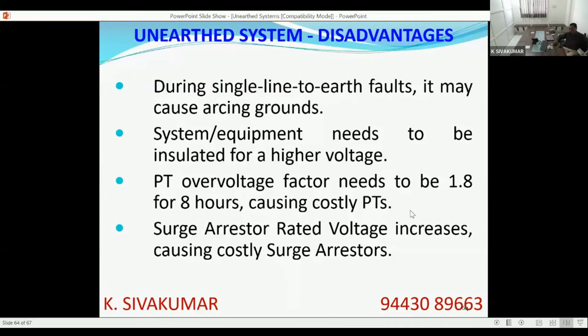If they say 11 kV E or 6.35 kV UE. In fact, for a 6.6 kV UE system, you practically have to use an 11 kV cable. So 11 kV E is equal to a 6.35 kV UE system. Every time an unearthed system is there, you have to use a higher rated cable and higher rated equipment. So that will make your system costly.